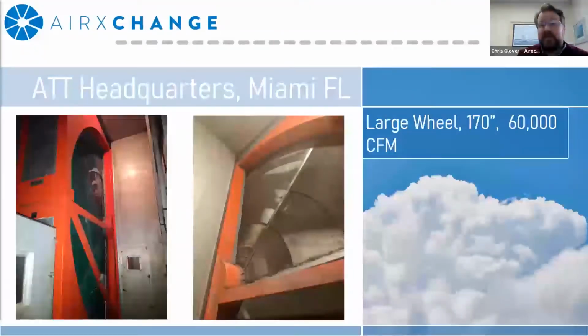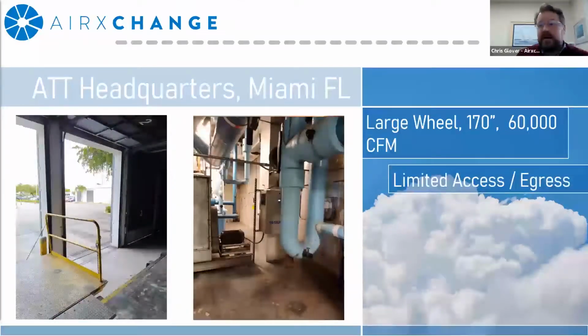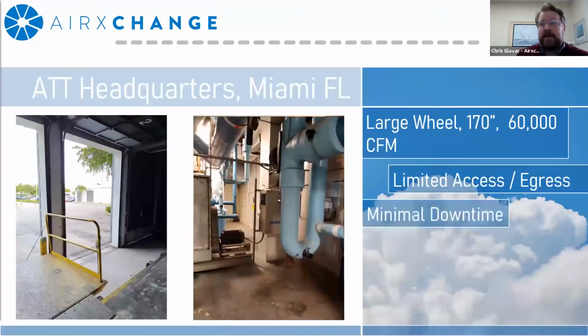The original media failed due to severe plugging over time. The wheels got very dirty, and the owner couldn't clean them, which caused the wheels to fail. It was a really big energy recovery wheel. So it's 170 inches in diameter, roughly 60,000 CFM of outside air in Miami. So you can imagine how much air conditioning load that placed on the building. So this project was unique in a couple of ways. Once again, it had very limited access, and it was in downtown Miami. So this is limited access to the building, limited access on the street.